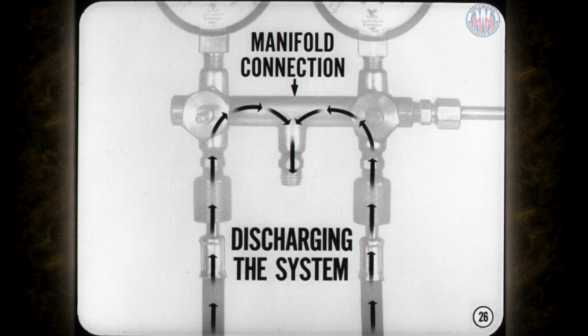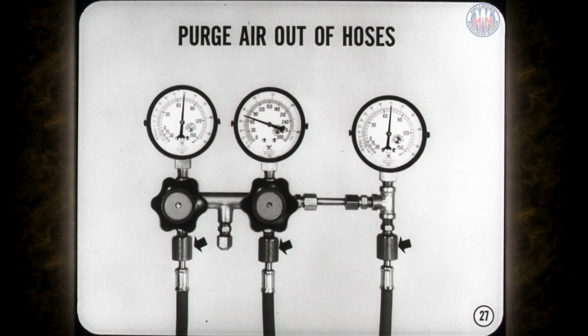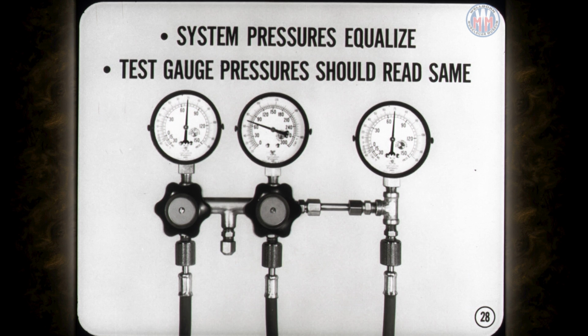Now, when you connect the hoses, first screw on the couplings finger tight at the compressor service ports. Then momentarily loosen the couplings under the connected gauges to purge air out of the hoses. If the gauge set has a needle valve, make sure it's partly open before you start checking system pressures. You begin testing with the engine shut off. Remember that system pressures gradually equalize and become static when the system is not operating. So test gauge pressures should read the same after the system stands long enough to stabilize.